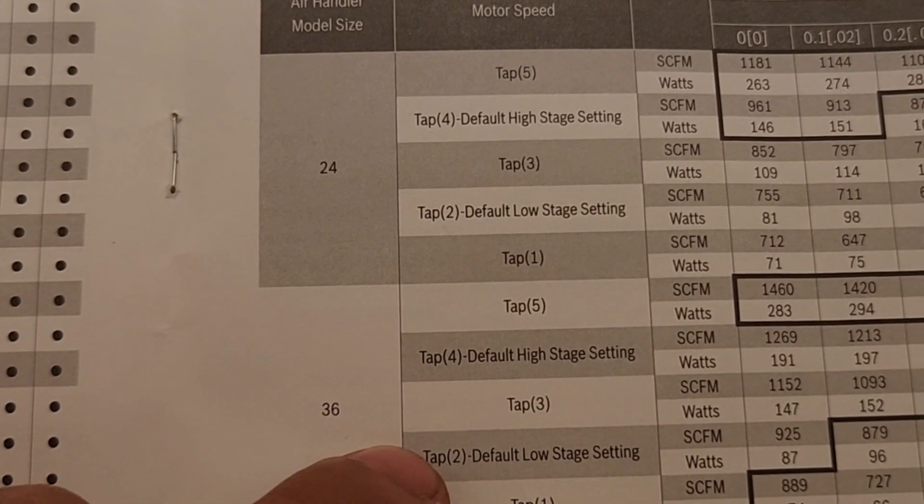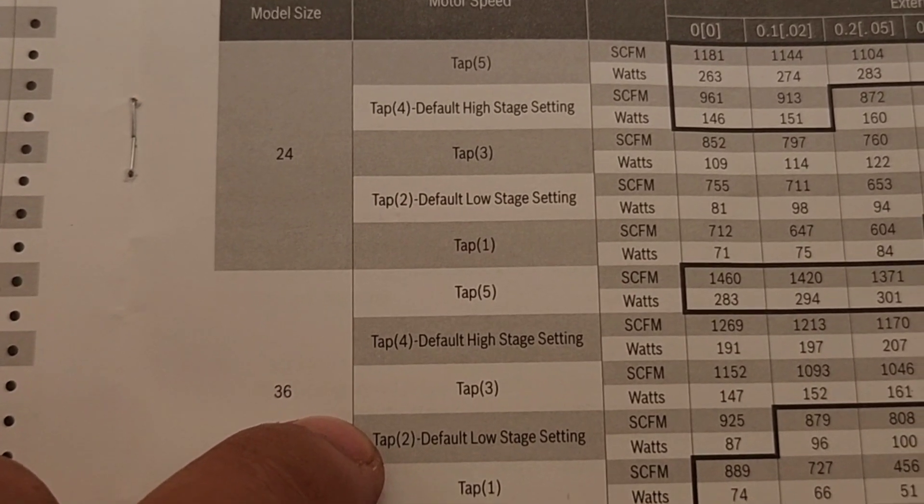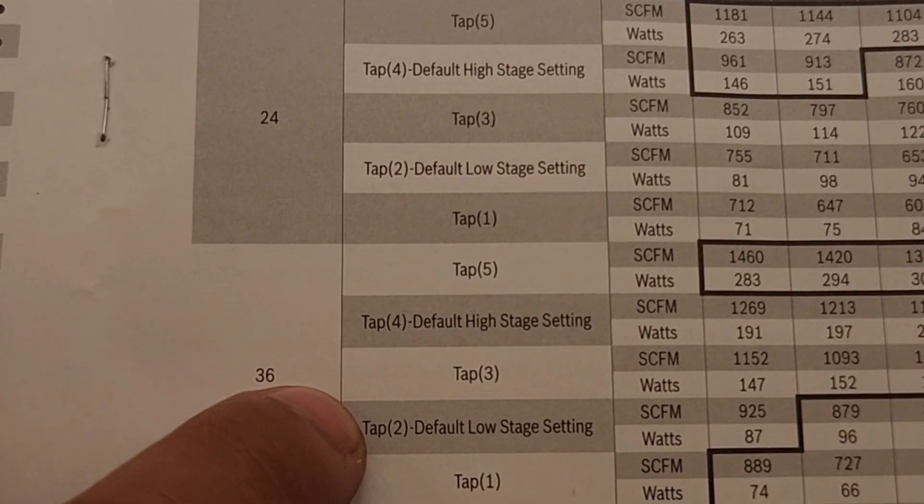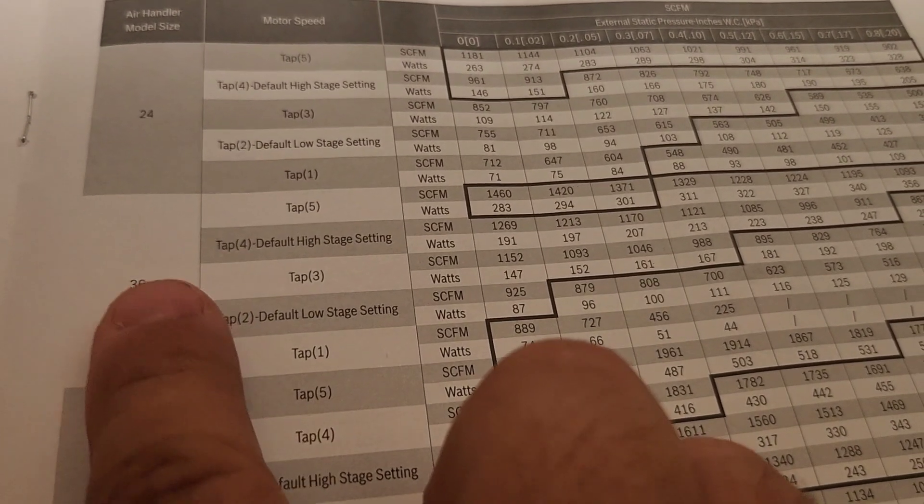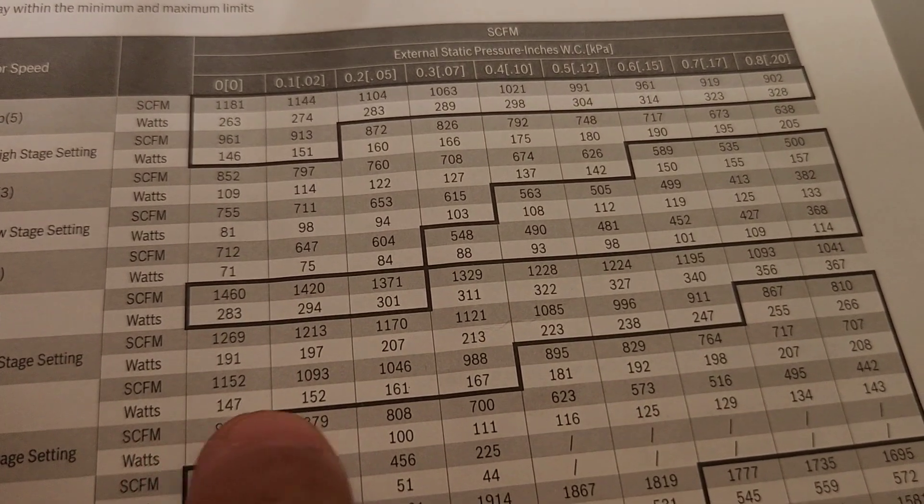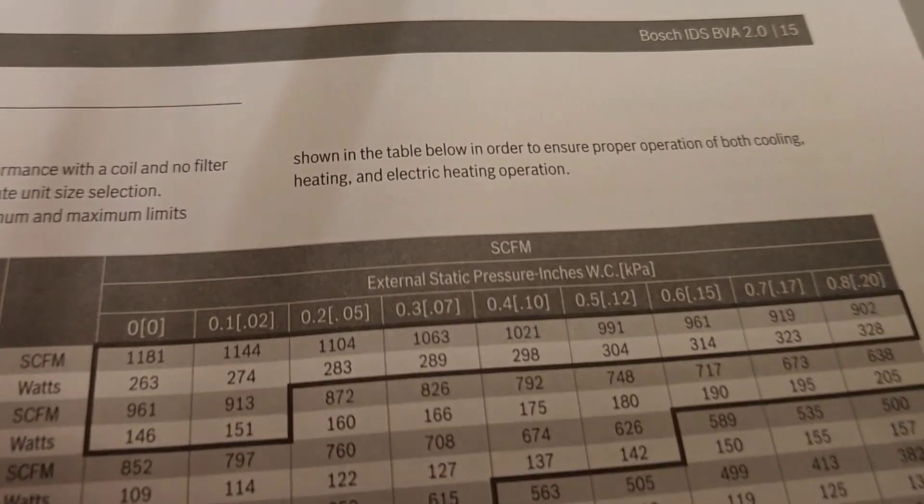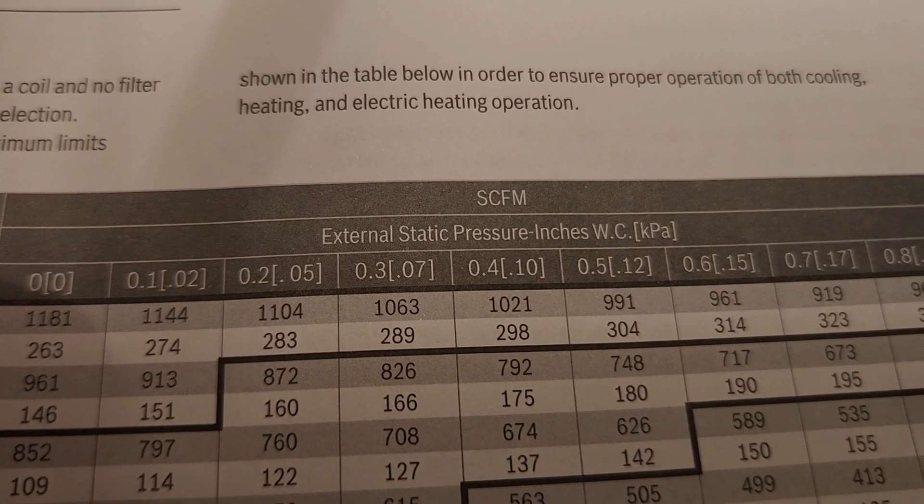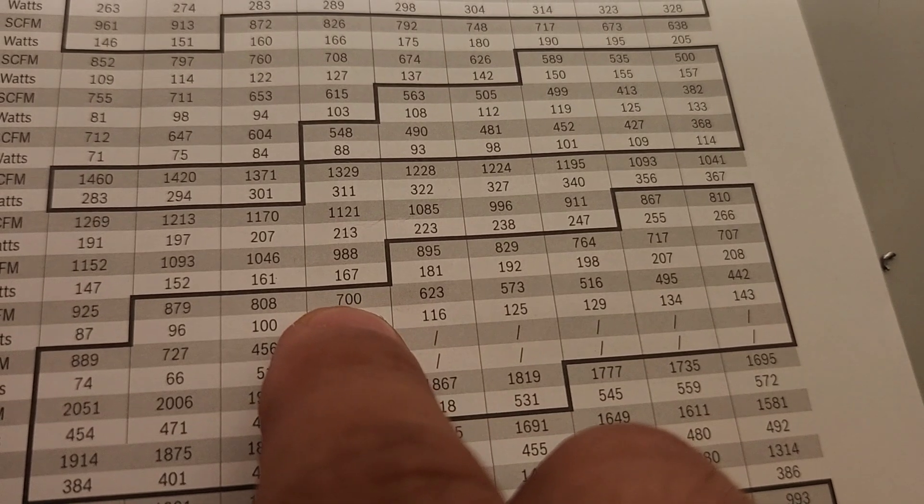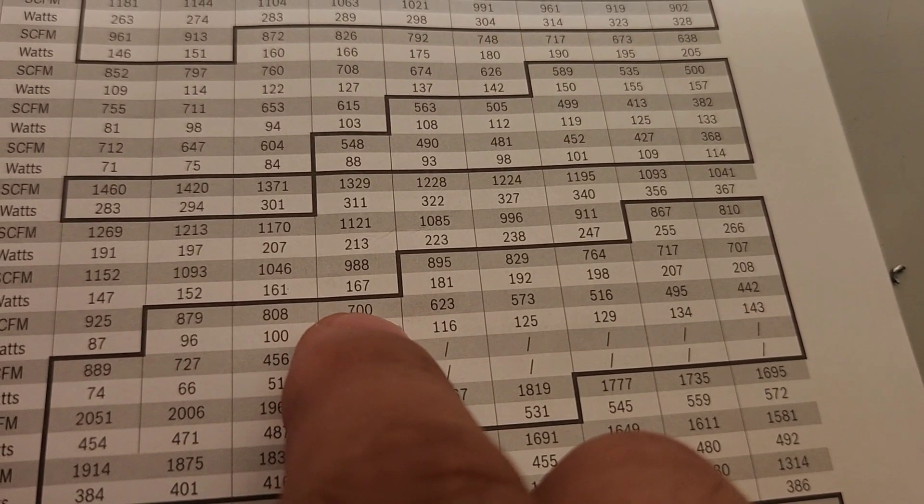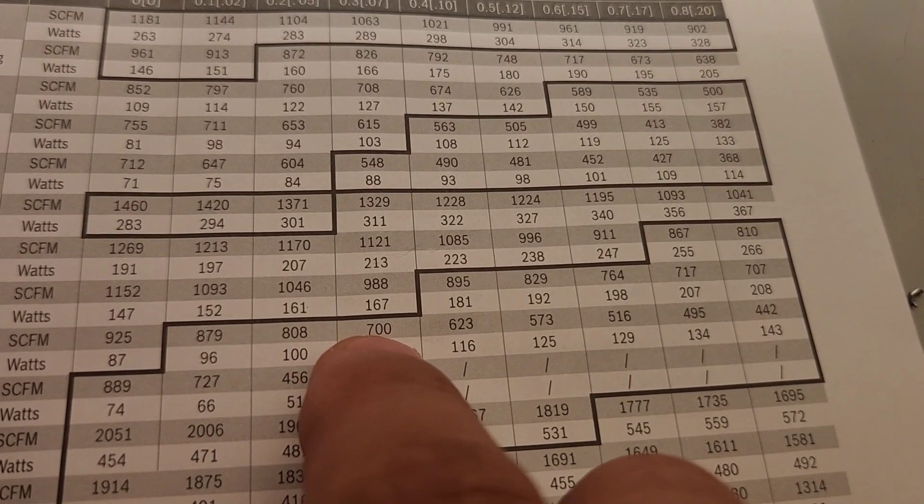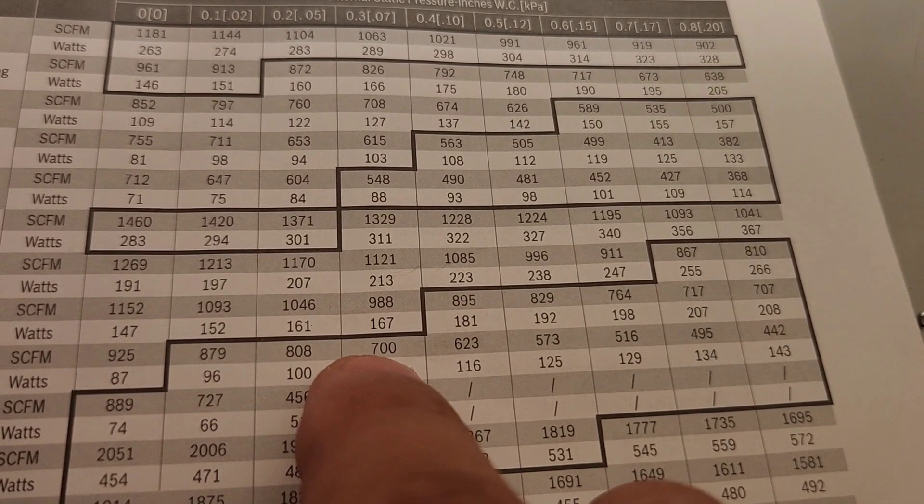So we're going to go with this speed tap two because that was the tap that was being used during that static pressure test. All right, so we've located our air handler, we know which line of these five settings, and next thing we've got to match where this line intersects with the static pressure that we read. So if you recall, we were reading 0.25. So that's going to be somewhere between 0.2 and 0.3, right? Well, looks like we're somewhere between 808 and 700. So somewhere maybe around 750, 760 CFMs, a little bit of interpolation has to be done. And that's one of the limitations of this test. You're not going to get an exact number, but at least by doing this test, you're going to be in the ballpark.